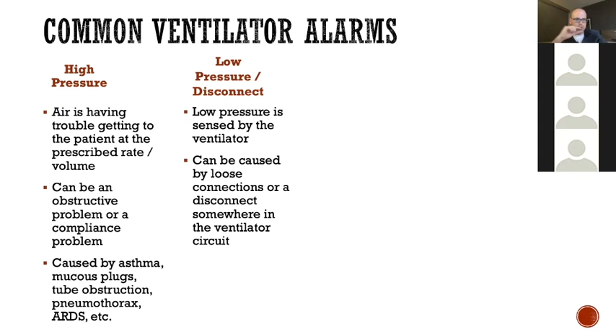Apnea alarms are not something you're typically going to get, because we're not going to have that on for a patient that is on a ventilator mode that's delivering the breaths. Apnea is more for a patient that's on something like pressure support ventilation when we're weaning them off of the ventilator, like we talked about earlier, where we're expecting them to be breathing on their own, then we would want to know that they've gone apneic. So it's not needed in patients that are on full ventilatory support.